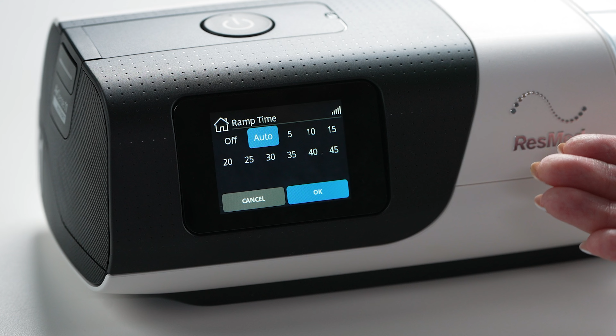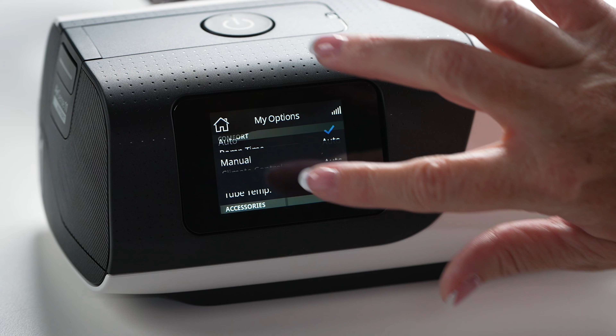Okay, let's talk about the menu settings. While the settings we're going to go over on this machine are specific to the AirSense 11, most machines on the market have very similar settings. So first, we're going to talk about the ramp feature. A ramp feature allows you to start out at the lowest setting possible and slowly rise to your set pressures. So here we're going to hit your ramp time. This machine has an auto feature. What an auto ramp does is allow the machine to increase in pressure after it has sensed you have fallen asleep. Additionally, you can set it for a timed mode. You can go as low as 5 minutes, as high as 45 minutes of a ramp, or you can even turn this feature off. Once you set that to your comfort level, just click OK.